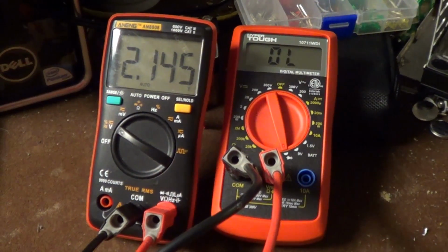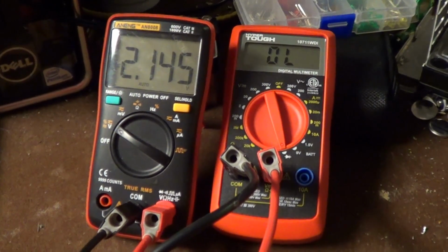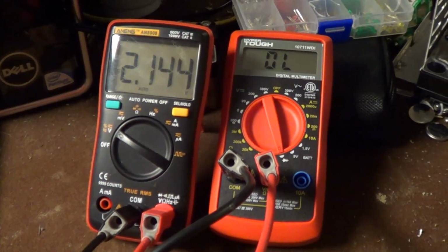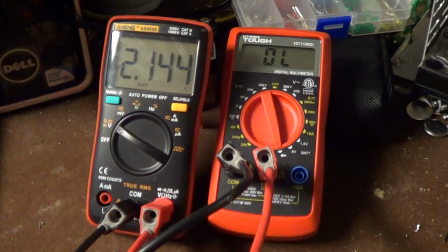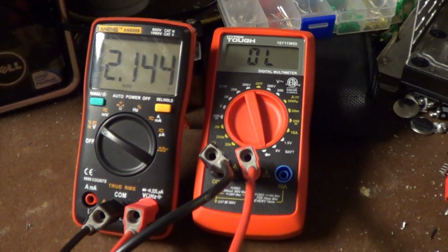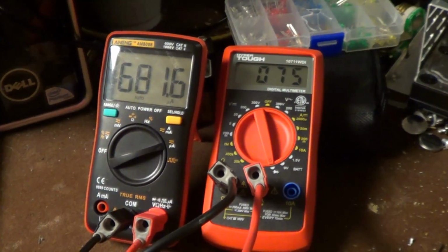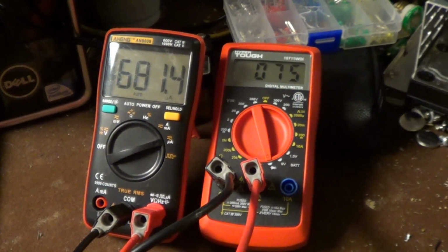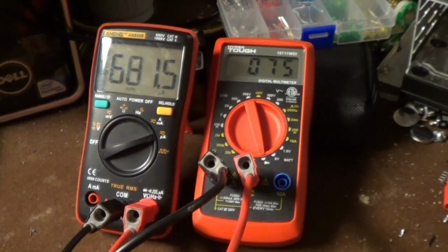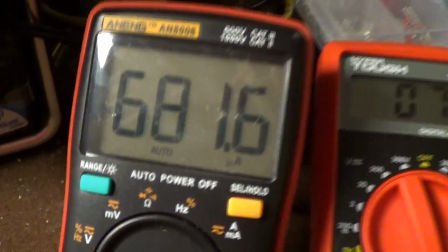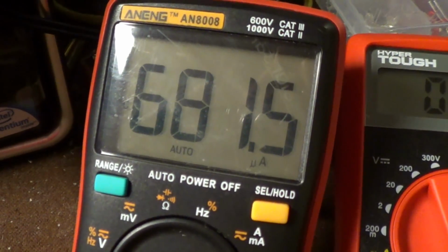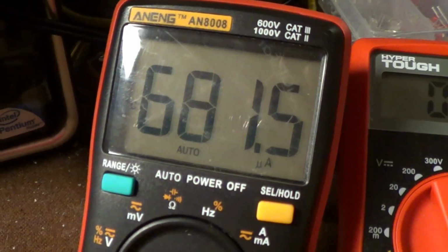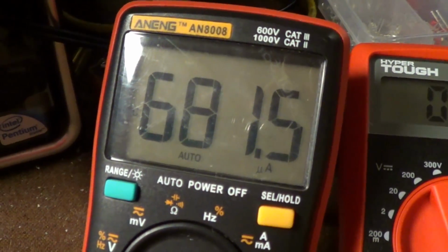The owner's manual indicates that the testing voltage for diodes is 2.2 volts DC, and that certainly seems close enough to reality. However, if you load it down to any significant degree, the available current for testing a diode is extremely limited, at right around 700 microamps or thereabouts. That's just not enough to test a lot of LEDs.